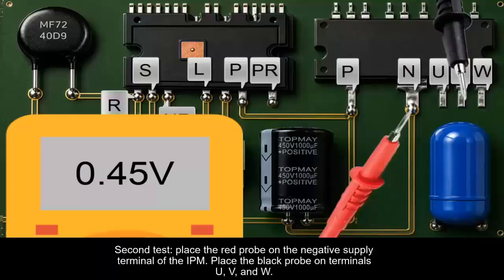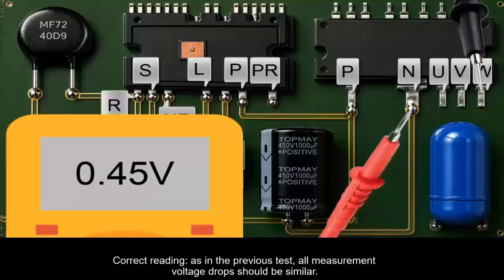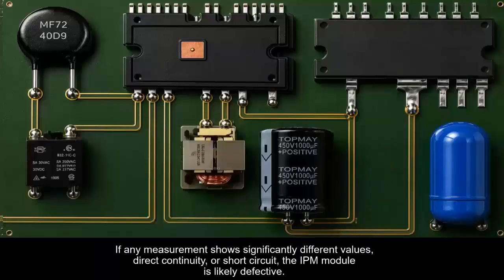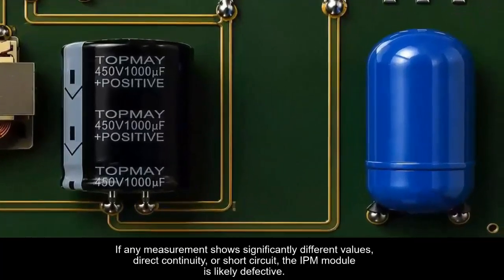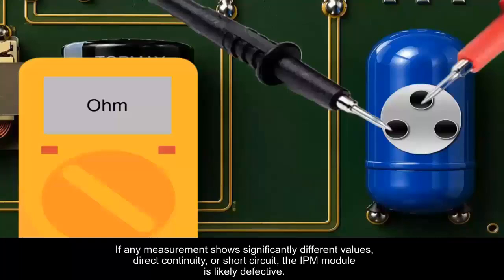If any measurement shows significantly different values, direct continuity, or short circuit, it is highly likely that the IPM module is defective and requires further evaluation or replacement. Inverter compressor diagnostic procedure. An error code may also be triggered by internal electrical problems within the inverter compressor. To perform the diagnostic procedure, completely disconnect the equipment from the power supply and then disconnect the compressor power terminals.